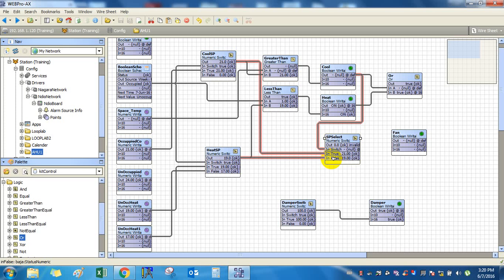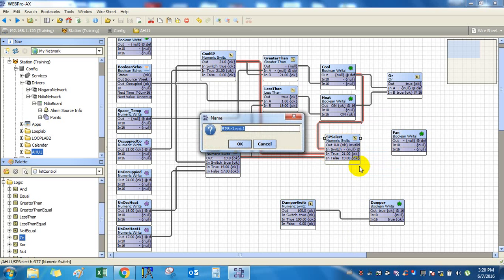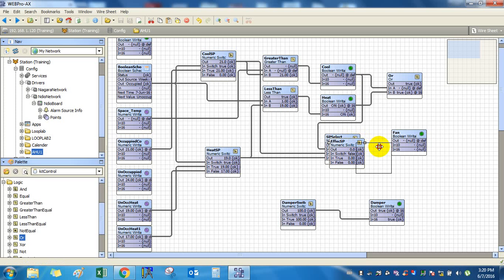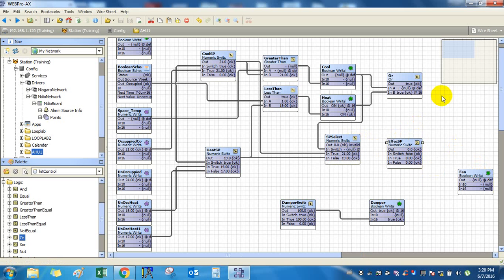Again I will take a numeric switch and name it as effective set point. So whenever there is heating or cooling in space, it will pass this set point. Otherwise it will directly pass your space temperature as set point, because we have kept 2 degrees centigrade as a deadband between cooling and heating. Your occupied heat is 19 and your occupied cool is 21. So if your space temperature is between 19 and 21, at that time your set point will be directly your space temperature. So that's how we write the logic for a simple AHU, that is your air handling unit.